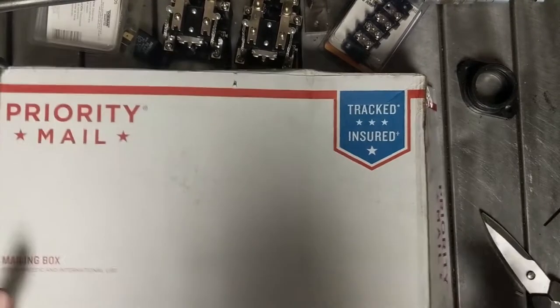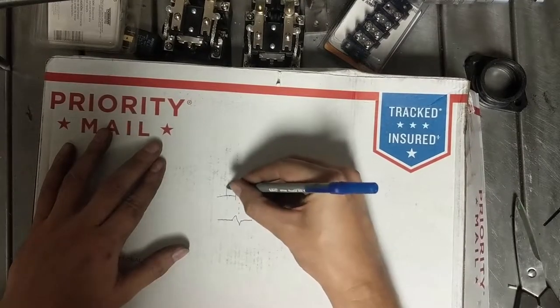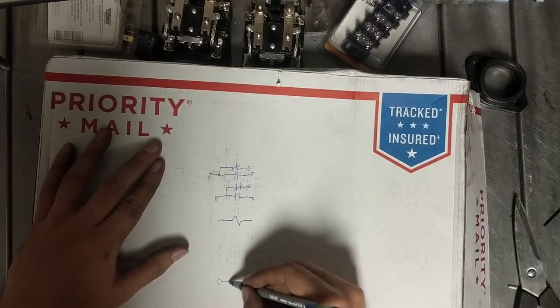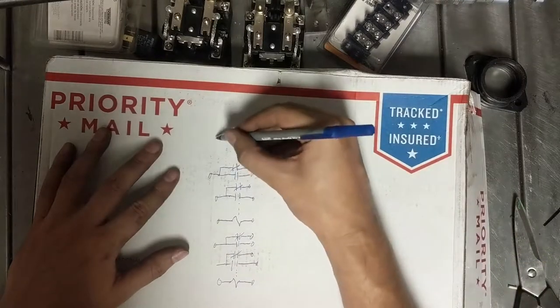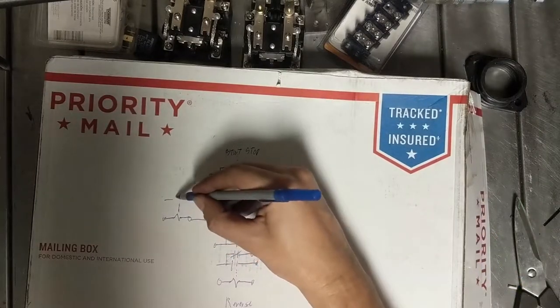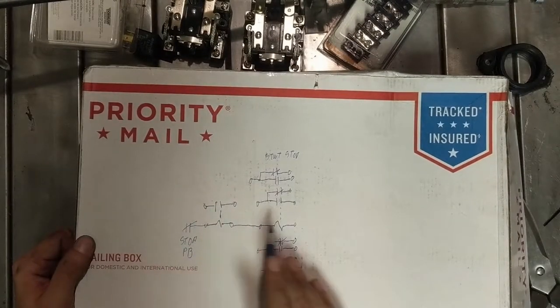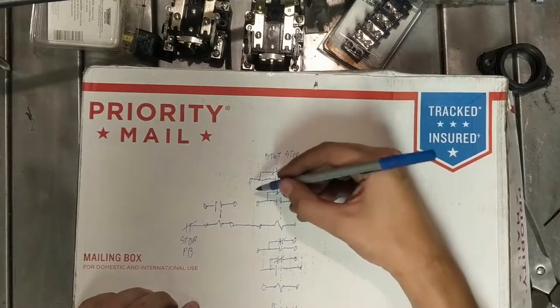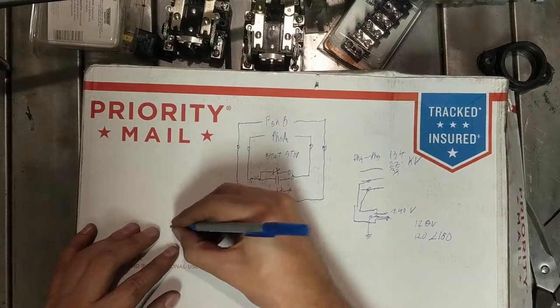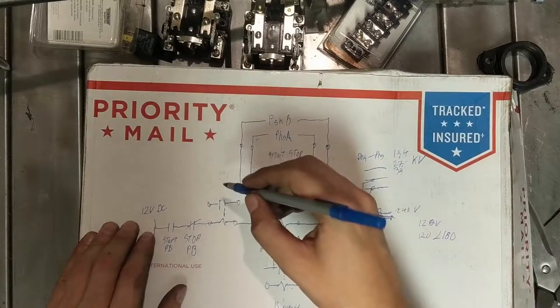Right here we've got our starting relay with normally open and normally closed contacts, and it has two sets of those. We have our forward reverse relay, and we have our seal-in relay. We're going to put that in series with our start stop relay, and this just has our one normally open contact. We want our normally closed stop switch to cut out this circuit here. The start stop relay cuts our phase voltage - phase A, phase B. We want our start push button to pick up this relay. What we don't want to have happen is we don't want to have to hold this start button down.